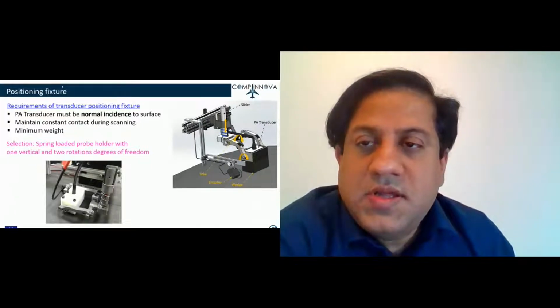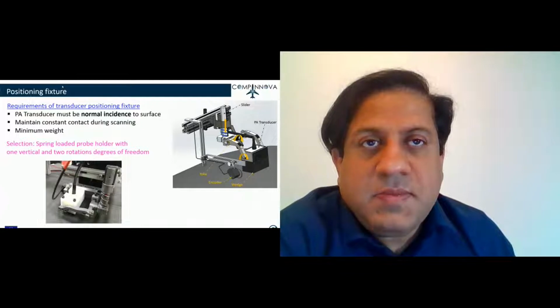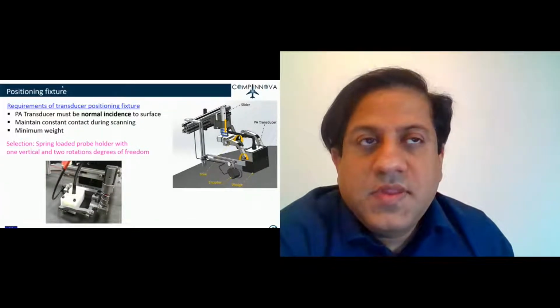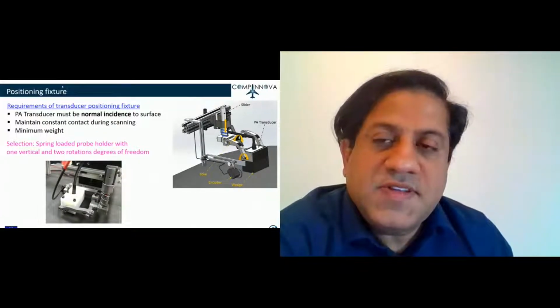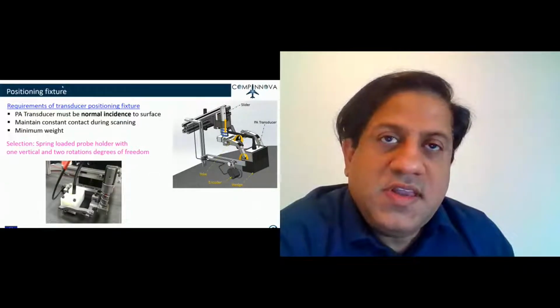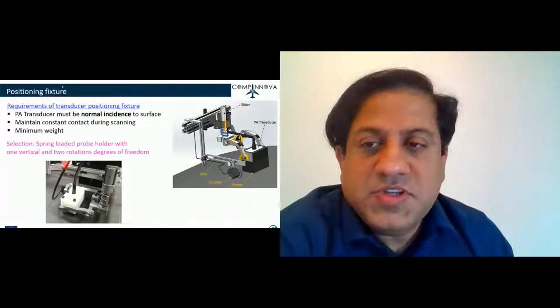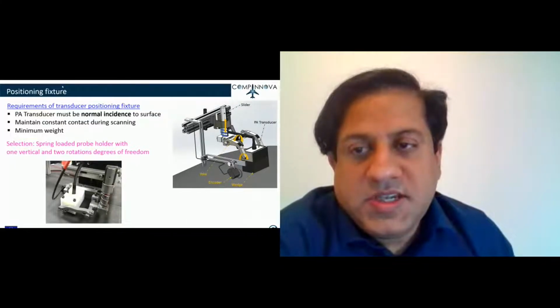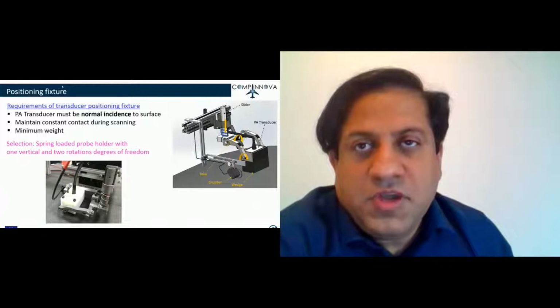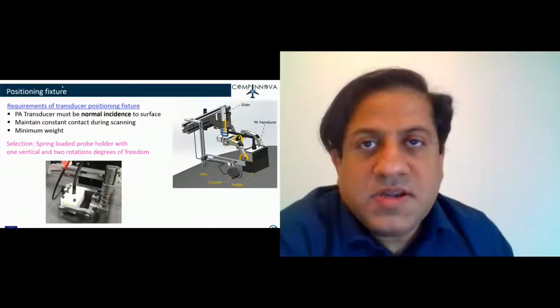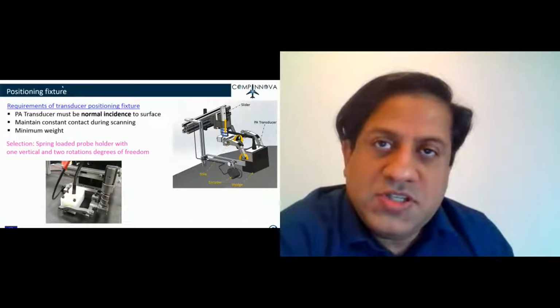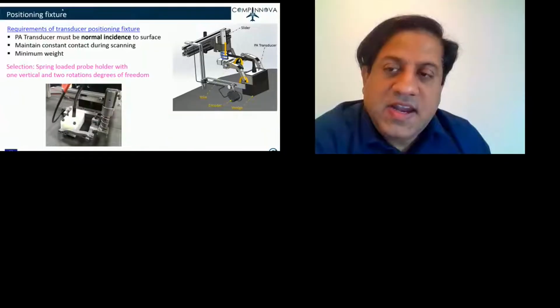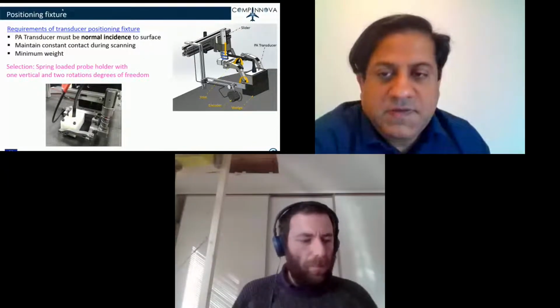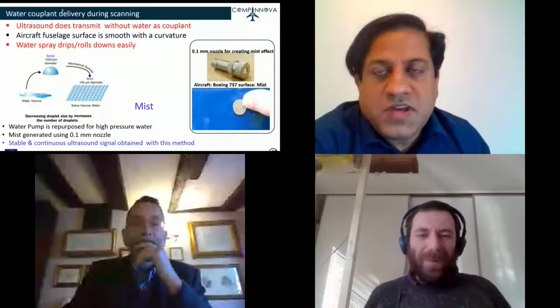Now coming to the water couplant. Water as a couplant is used with an ultrasonic transducer for coupling the ultrasound from the transducer to the surface. If there is no water, then there is no transmission of ultrasound into the surface, and hence it will lead to false positives. So in general, now they use either free flowing water or a spray of water. Free flowing water is not possible because of the robot constraints. And when we saw the spray of water, we found that it is not suitable for automated inspection.